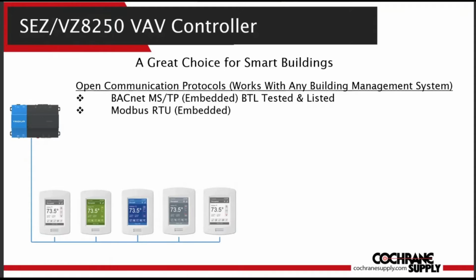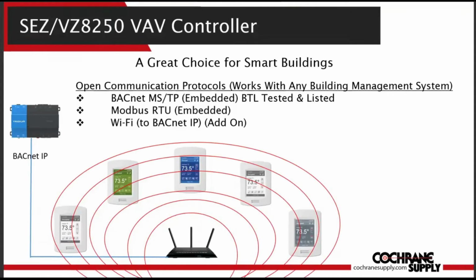These 8250 series room controllers also have the capability to communicate via Modbus RTU. So if you run across an existing installation that's got a Modbus network, there's no need to run a new trunk for BACnet. Just toggle the communications on the controller to Modbus and add it to the network. The controllers also support the addition of a Wi-Fi communications card. The room controller can connect to a Wi-Fi network router and can be used in standalone applications or connected to a building management system.